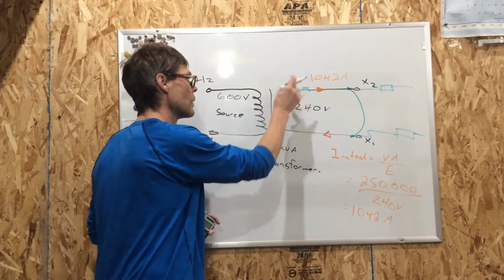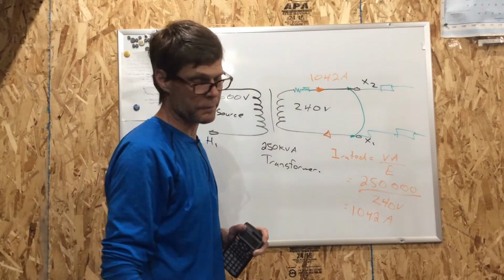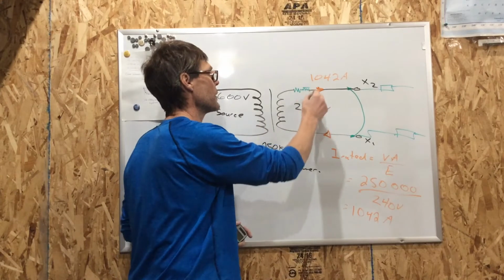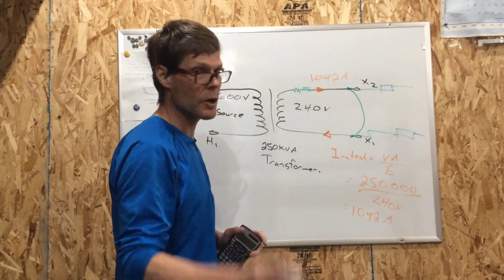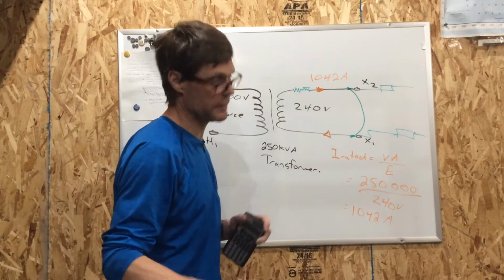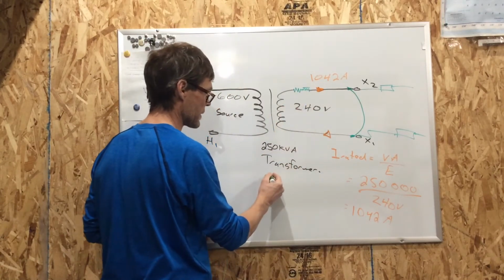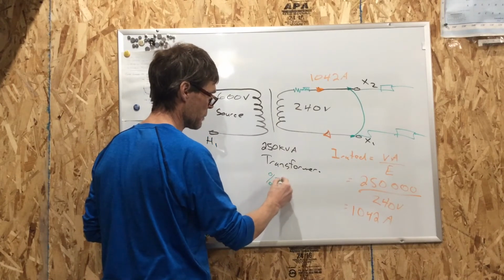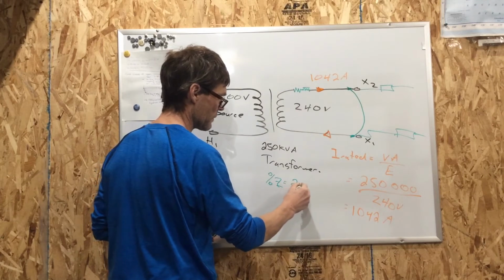So, what we have stamped on these is something called percent impedance. That takes into account this right here, and we'll talk about how we get percent impedance. Percent impedance comes from our short circuit current test.